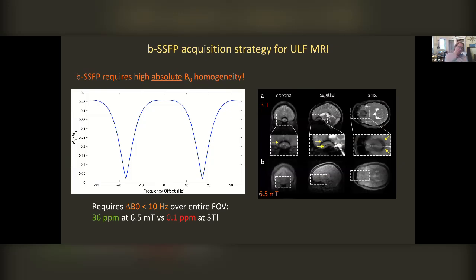So, of course, SSFP is an interesting sequence, but it's not used too much for whole head imaging at high field for a very interesting reason. What I've written down here is the steady state transverse magnetization as a function of frequency offset. So if you want to operate in this region here, where you don't get the so-called banding artifact, where the signal goes to zero, you need to hold an absolute homogeneity, not a fractional homogeneity, of less than around 10 hertz over your whole field of view. Very easy at low field. That's 36 parts per million at 6.5 millitesla, but that's 100 parts per billion at 3 Tesla, which, as all of you know, is impossible, because even if your magnet was shimmed that well, magnetic susceptibility artifacts from, say, the air sinus interface cause banding.